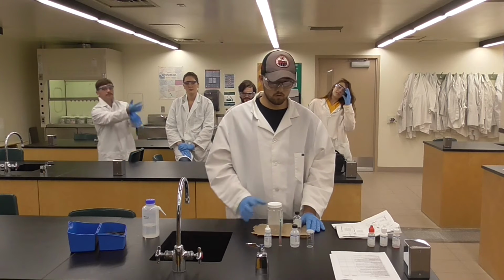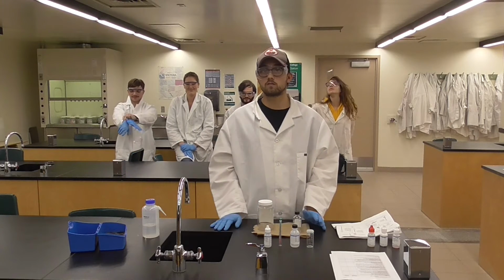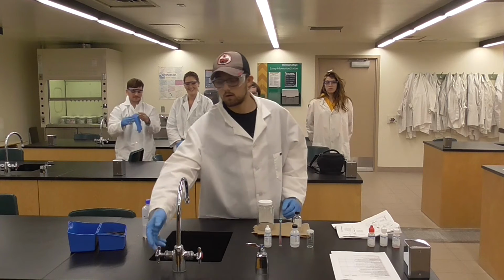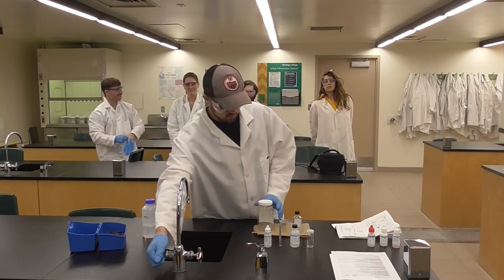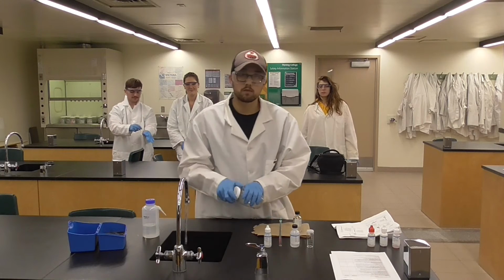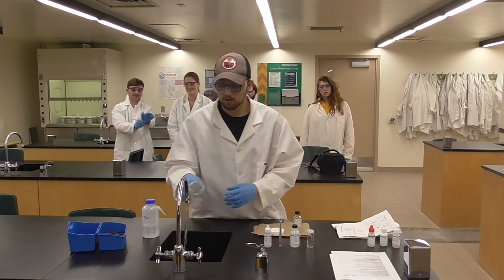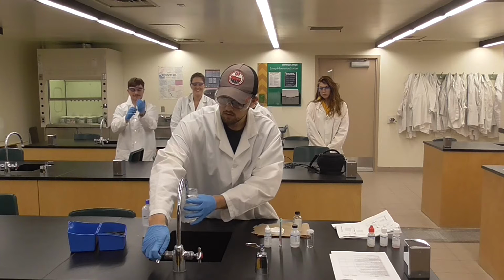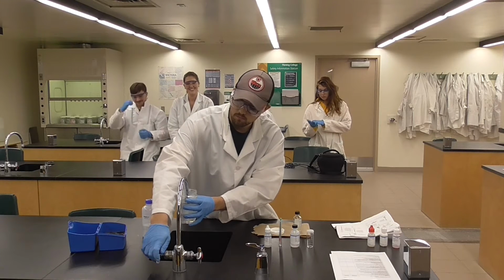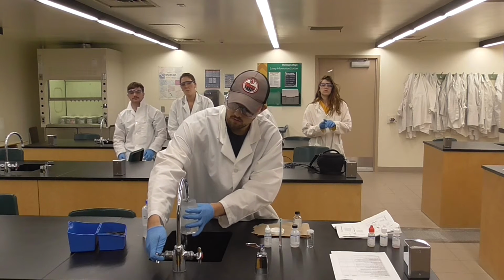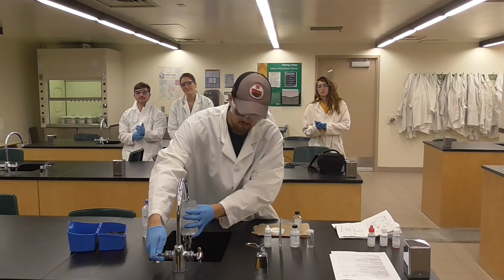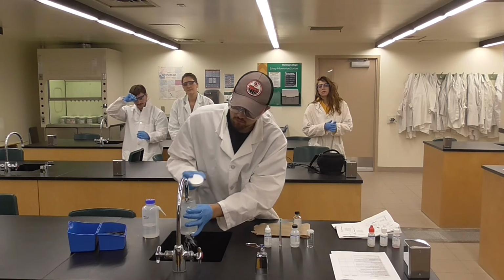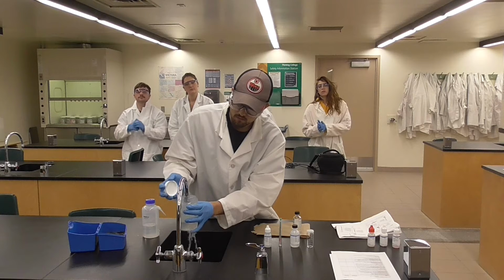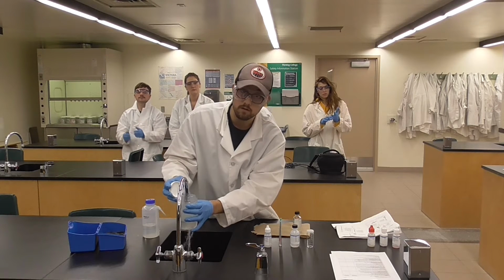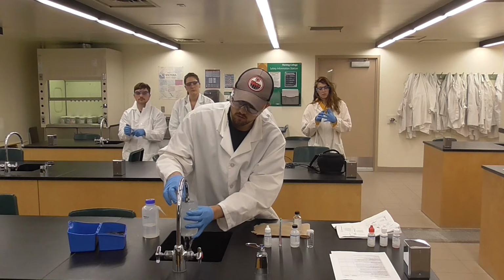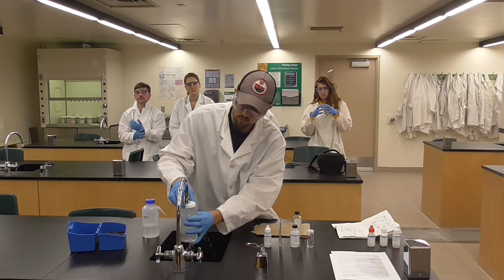So the first thing we're going to do is we're going to grab our water samples. For this lab, we're going to be using the tap. It's really important for the sample to have zero headspace, especially when you're measuring in dissolved oxygen, just because a little air bubble could make a larger difference in your overall sample. It's also important that you grab your titrator sample from the exact same spot as your larger PET 200 or 500 sample.